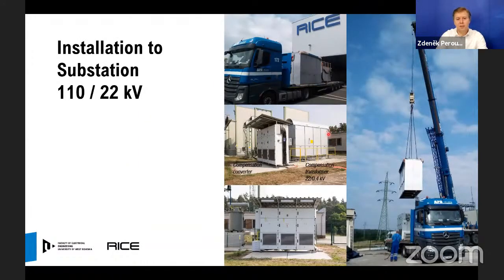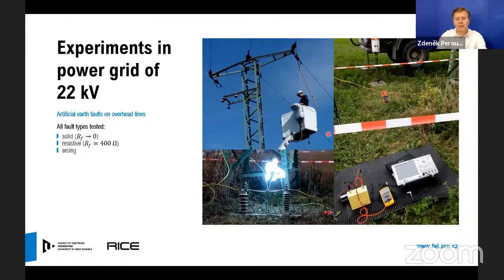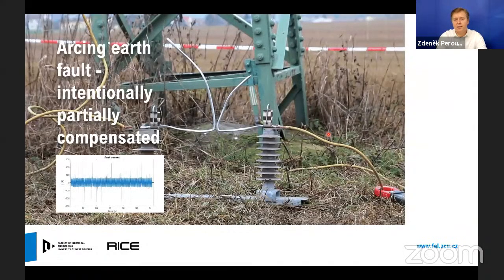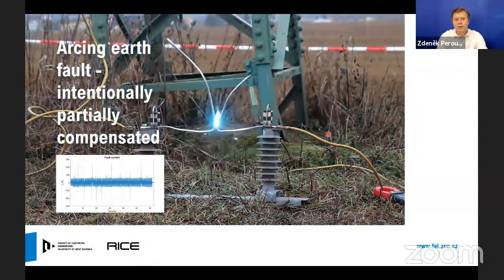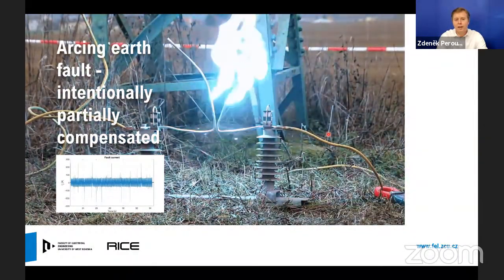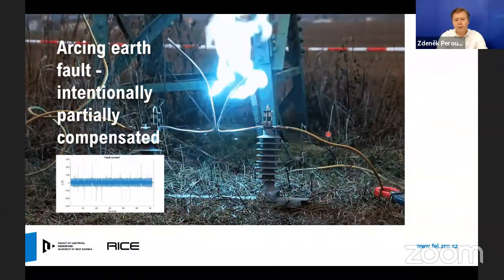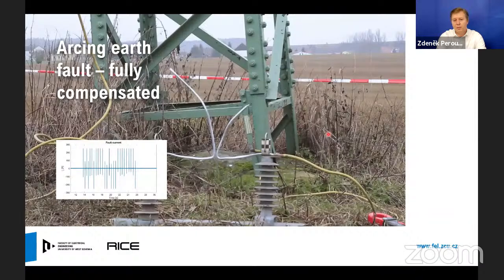After the laboratory test, we installed our prototype in a 110 to 22 kV substation and started the tests in the field. We started with artificial earth faults on overhead lines. We tested all fault types: solid, resistive, as well as arcing. Here you can see an illustration video of what happened when you face an arcing earth fault, which was intentionally only partially compensated. In the second video, you can see the behavior of the system when our device fully compensates the ground fault.